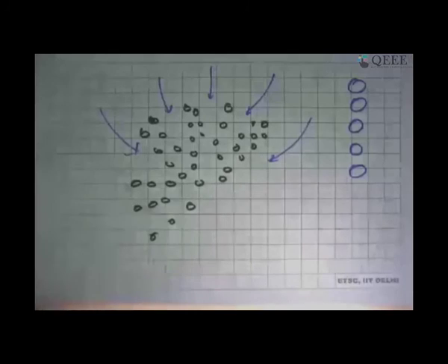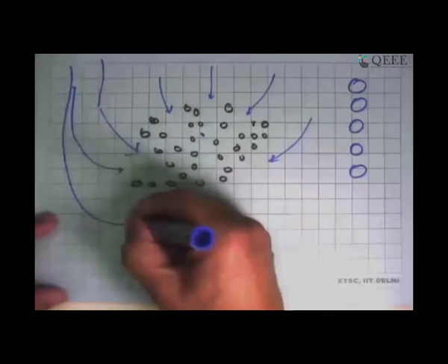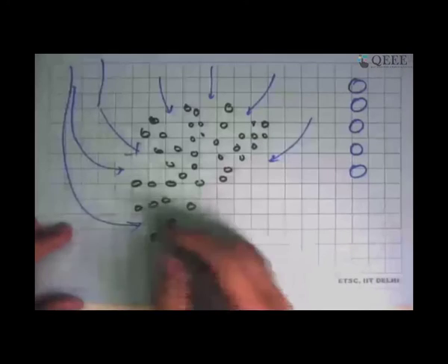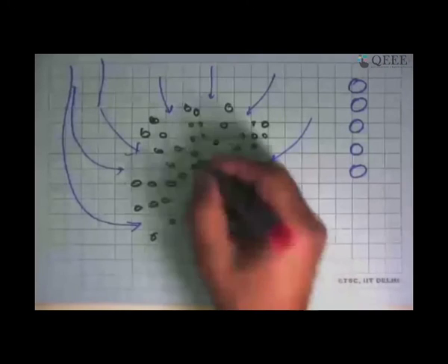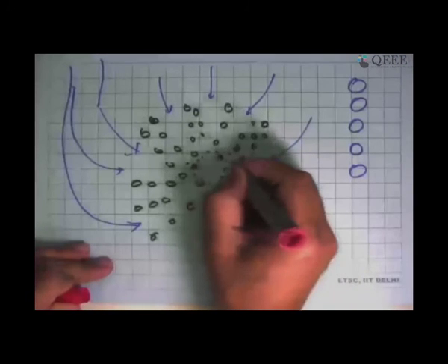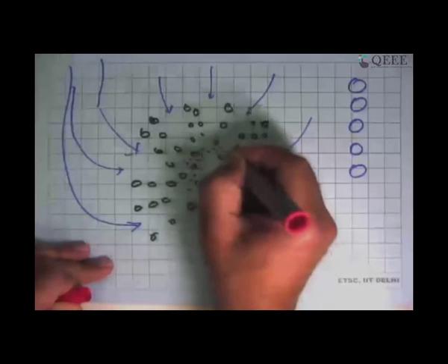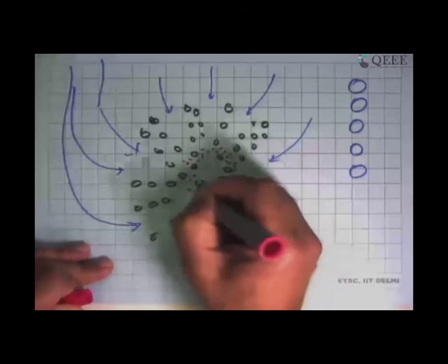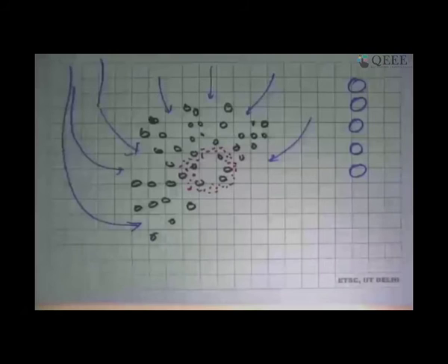So the steam coming from the turbine, which is coming from the top, is given multiple passages to penetrate the tube bundle, and all these non-condensable nitrogen and oxygen which were there begin to accumulate in this area. So we increased the heat transfer coefficient one way. That was a nice thing for us. At the same time, we pushed nitrogen and oxygen to one part of the condenser tube bank.